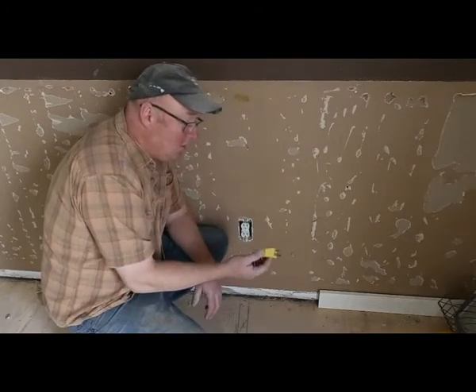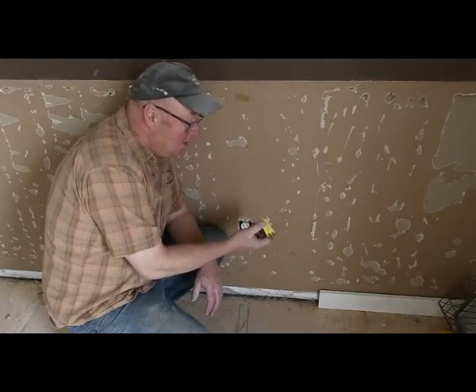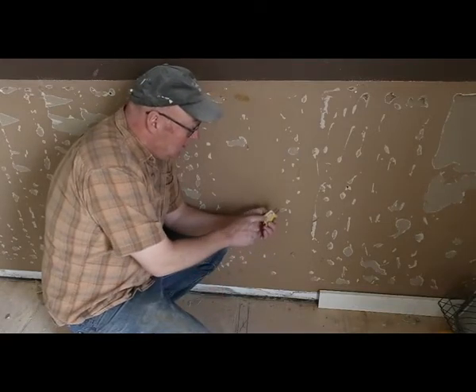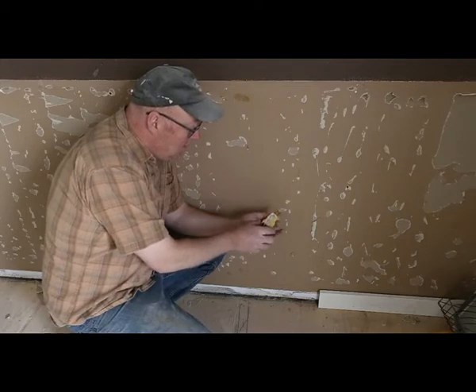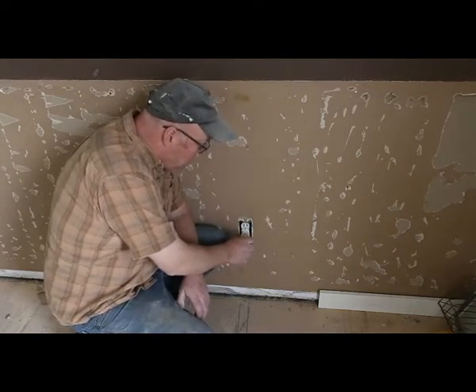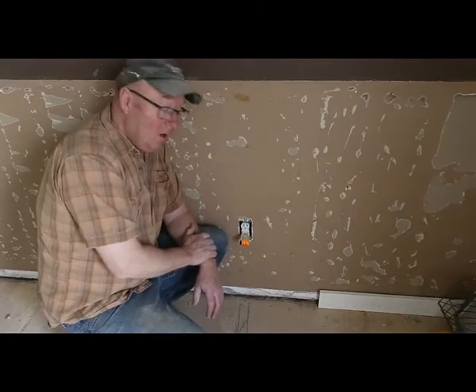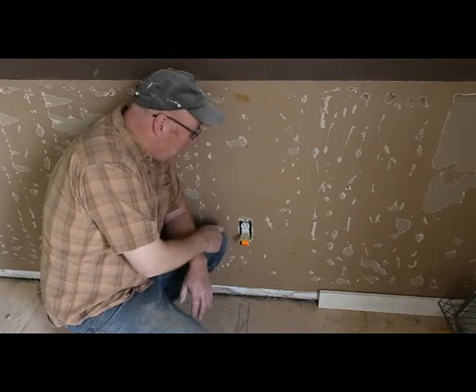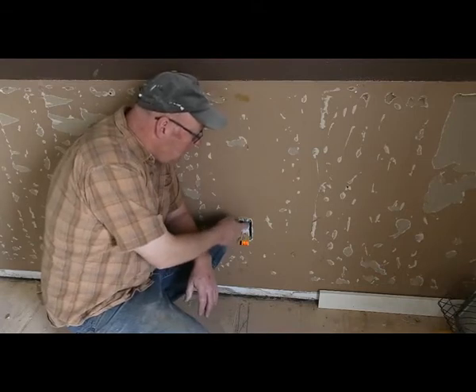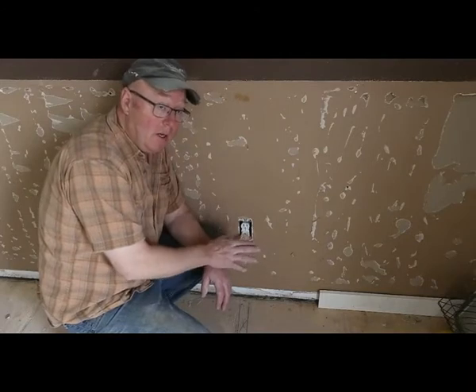And if you're doing some electrical work, it's a really good idea to pick up one of these, just test your circuit. It tells you what you've done wrong, and it's perfect. If I put it in this one here, you're still pretty good. For the most part, most people plug in at the top of the plug, and that's the one that's going to wear out. It's worn out. Don't take a chance on arcing or anything like that. Change them.